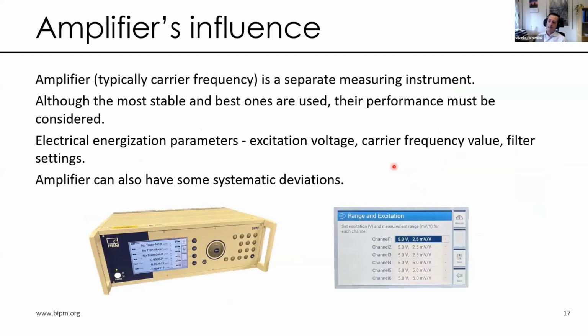Right, and also the influence of the amplifier has to be considered. The amplifier that we normally use is a carrier frequency amplifier, and it is of course a separate measuring instrument. So we try to take the best in the world that is available to minimize the influence of this instrument, but of course its performance must be considered. The typical energization parameters that may affect the results are the excitation voltage, the frequency value, and also the filter settings. These are examples given for this type of measuring amplifier. Such an amplifier can also have some systematic deviations. Andrea will talk more about how to deal with them.